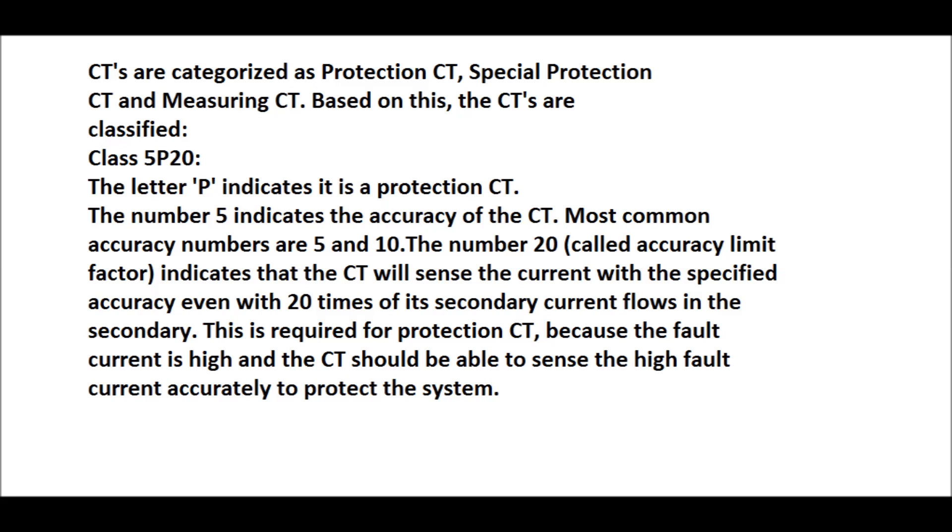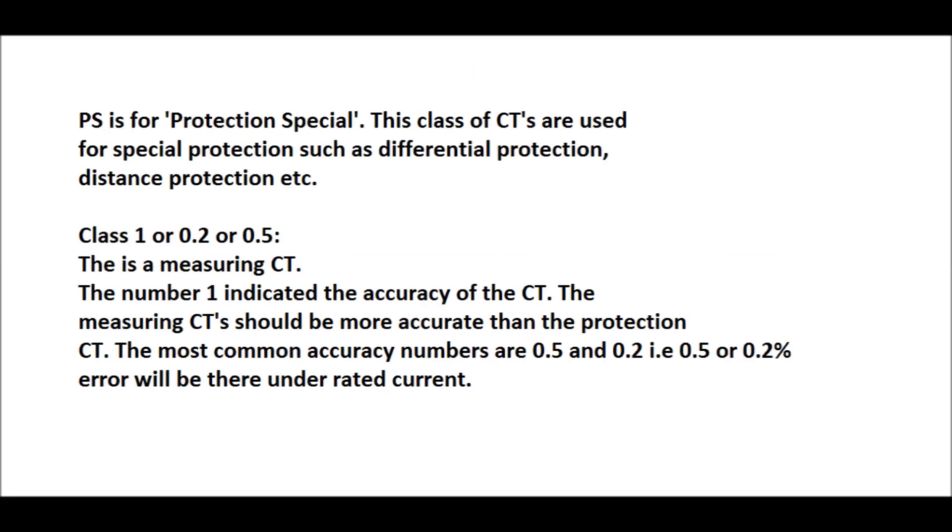Class PS is for protection special. This class of CTs are used for special protection such as differential protection or distance protection. Differential protection are used in transformer or in reactor and distance protection are used in line above 66 kV or 132 kV, 400 kV, 220 kV, 765 kV etc.